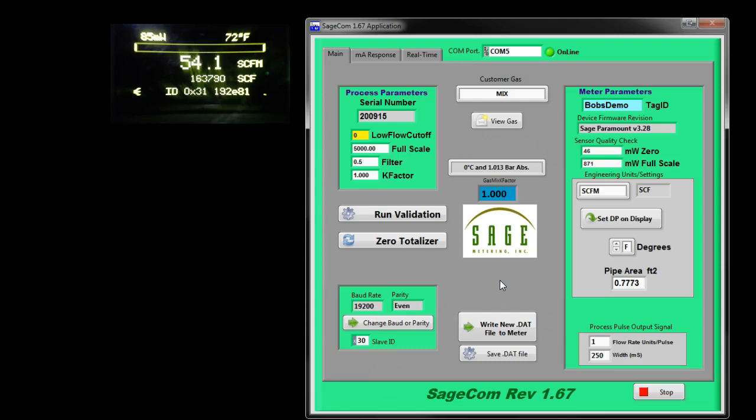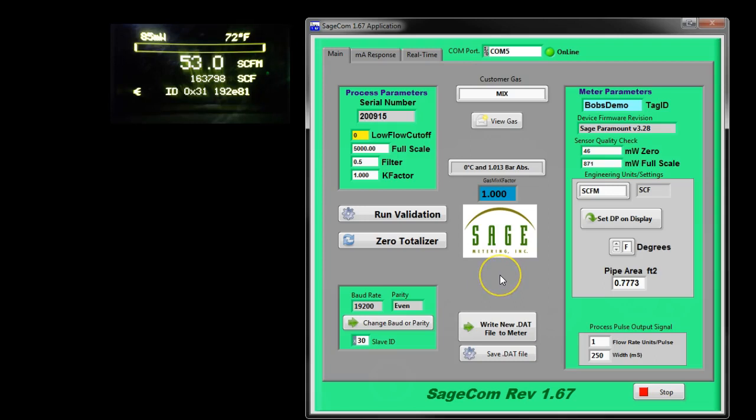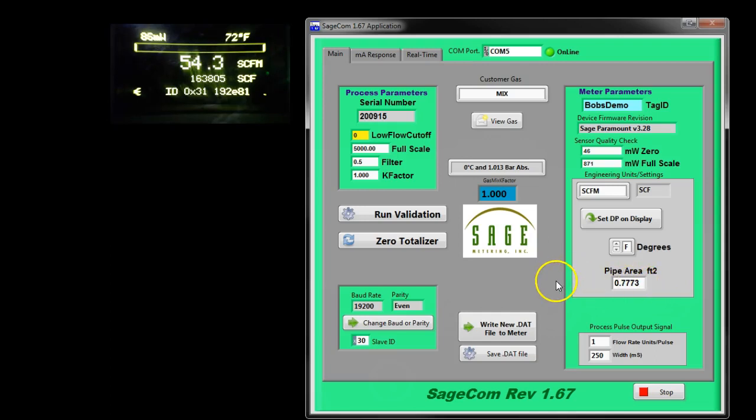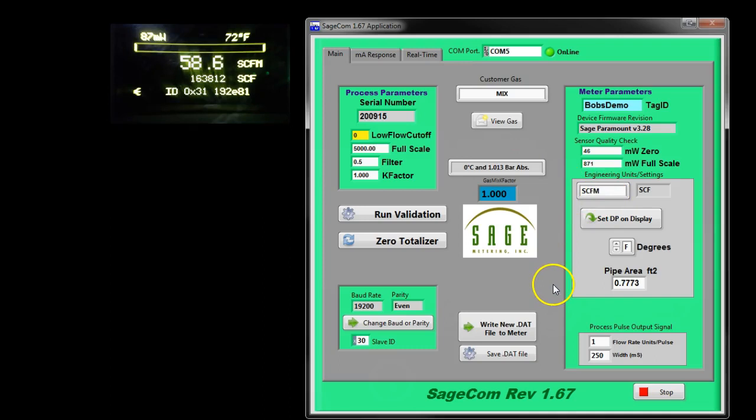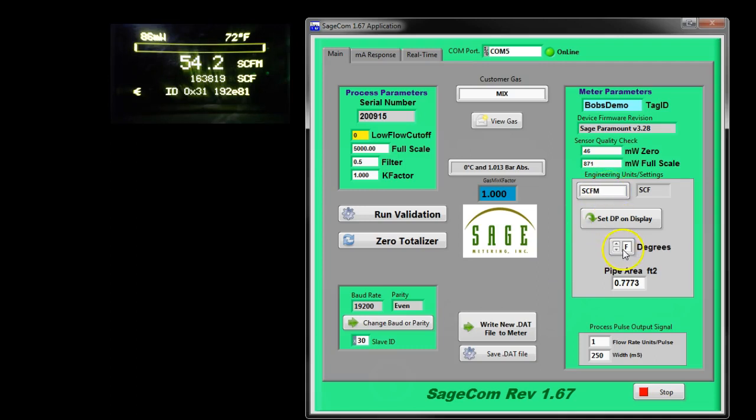You certainly can change the pipe area. Our instruction manuals on every product in the earlier pages show the cross sectional area in square feet of every pipe size. This particular cross sectional area is for a 12 inch schedule 40 pipe. This particular meter, the Sage Paramount, is set up for 5000 SCFM. Now I'm going to go through a few different examples of fields you can change. Engineering units can be changed, temperature can be changed, pipe area can be changed.